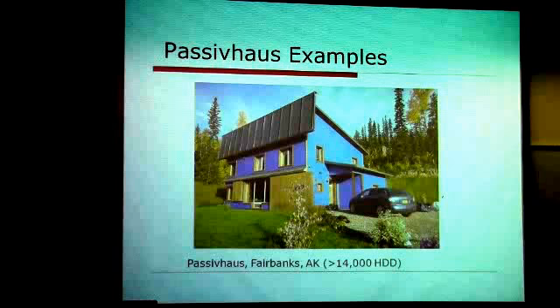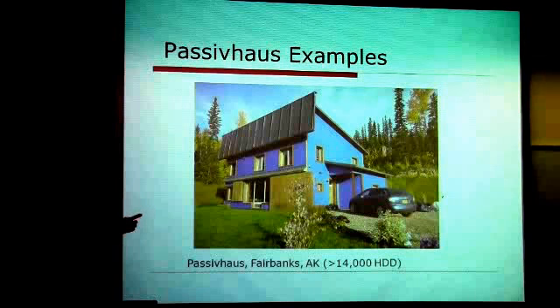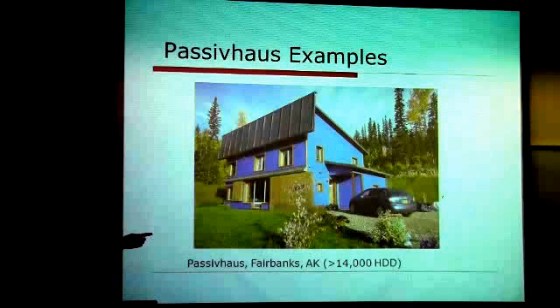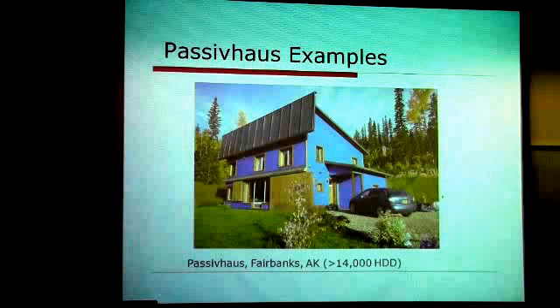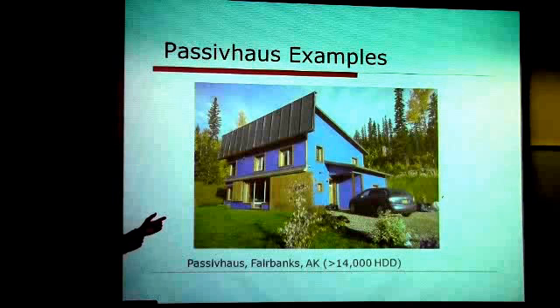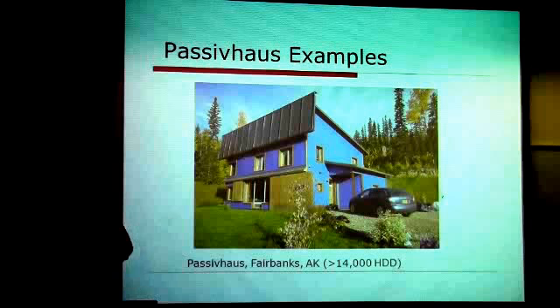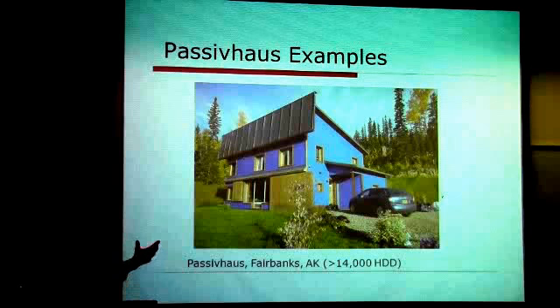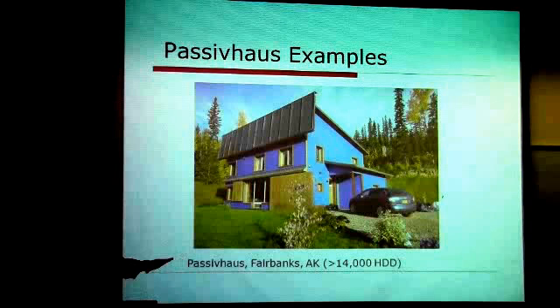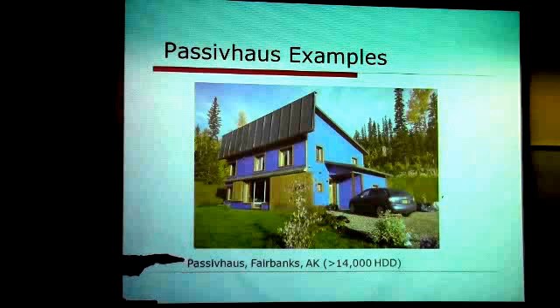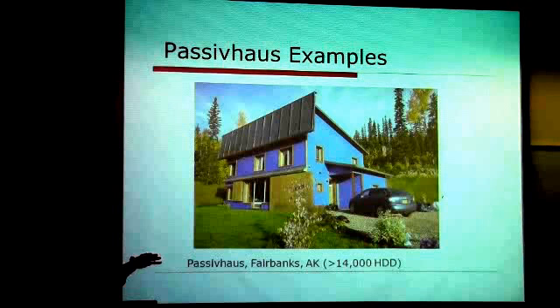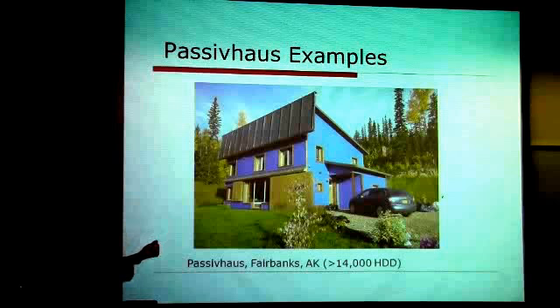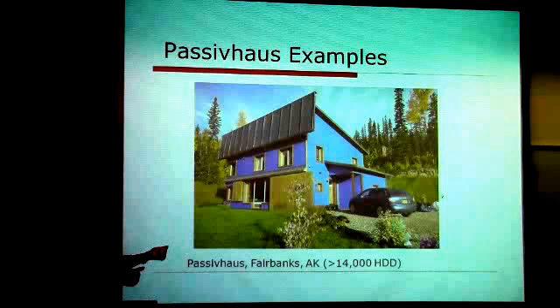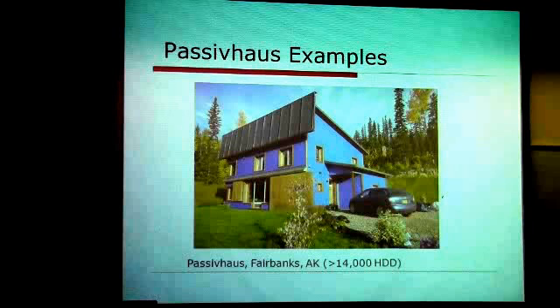He's doing a radiant floor system. He's got HRV in there, and then he's got the ground loop. So even when, this is Fairbanks, so it's much colder than Anchorage. So even when it's negative 50 outside, and the ground temperature might be, even though it's permafrost, near freezing, it'll still warm it up from negative 50 close to freezing, and that'll be enough so the HRV doesn't have frost issues and get that air in there.